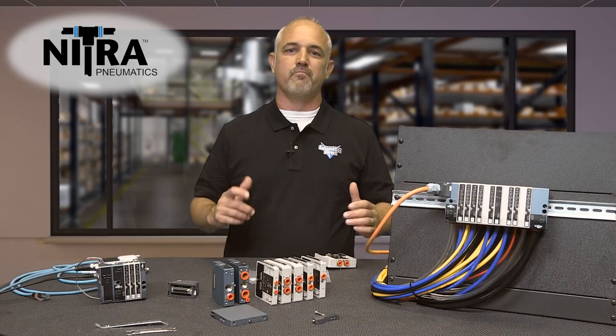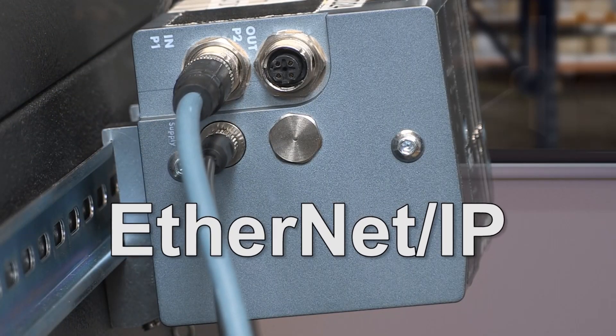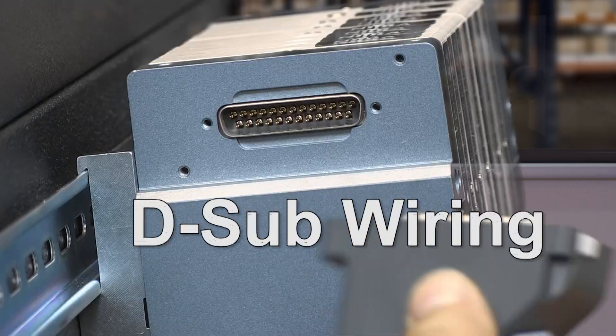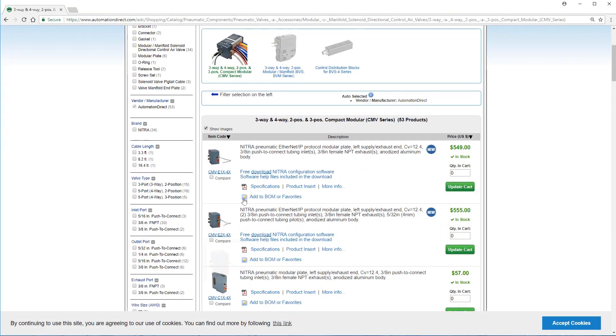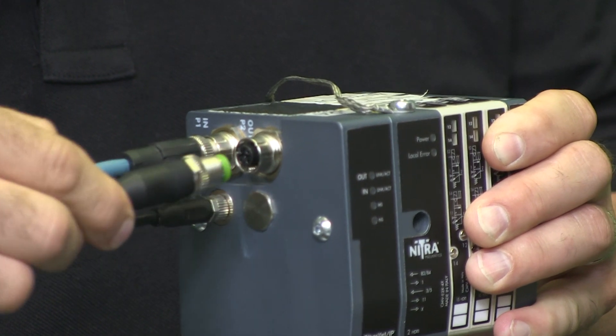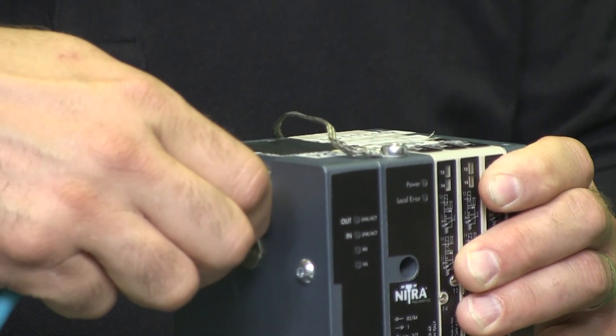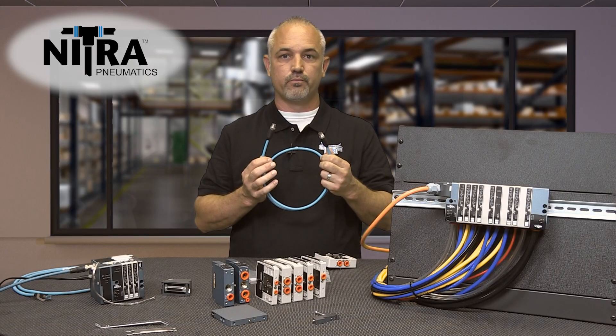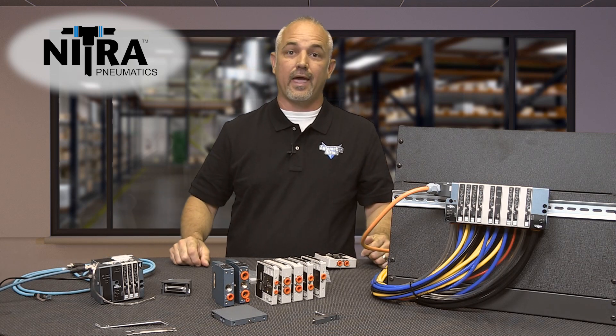Some of the features and benefits of these NITRA CMV valves are: select between Ethernet IP communications module or a standard wiring with a D-sub connector module. When using the Ethernet IP module, the system is configured with the free NITRA EIP configuration software. The Ethernet IP modules can be daisy-chained from one module to the next by using these 12mm Ethernet communications cables, simplifying control communications and wiring.